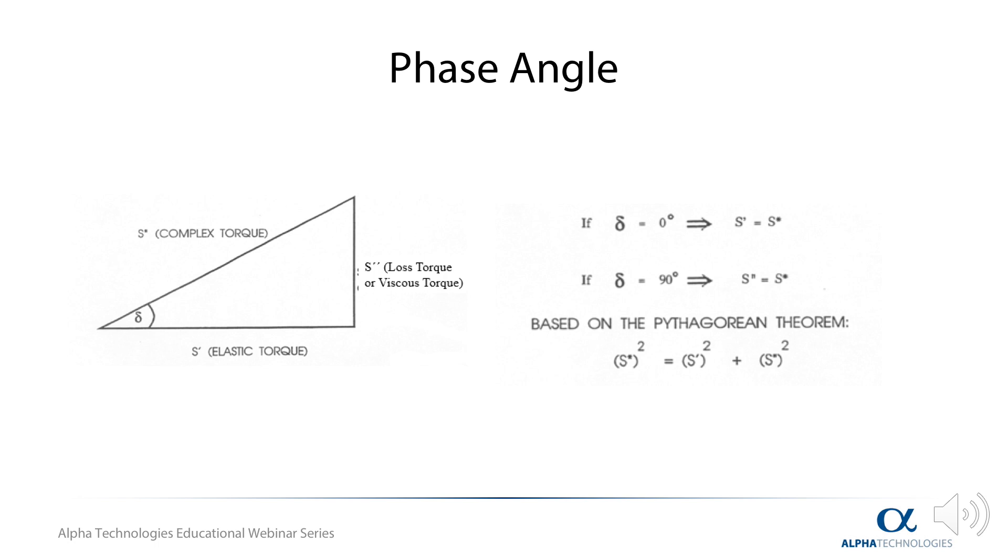The torque signal can be shown by the following vector, where the elastic torque and the viscous torque are 90 degrees out-of-phase. This is the angular difference, or lag, between stress and the sinusoidal applied strain. S prime, or G prime, is the elastic or storage component of the material. This determines the amount of energy stored in the material. This vector is in-phase with the strain position.